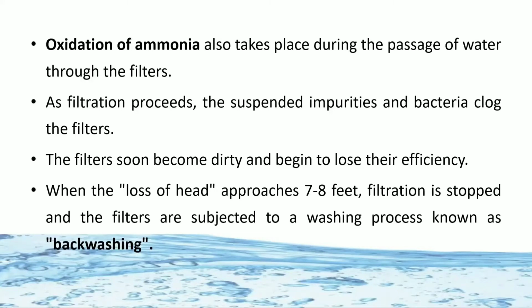When the loss of head approaches 7 to 8 feet, filtration is stopped and the filters are subjected to washing or cleaning. Here, the cleaning process is known as backwashing.